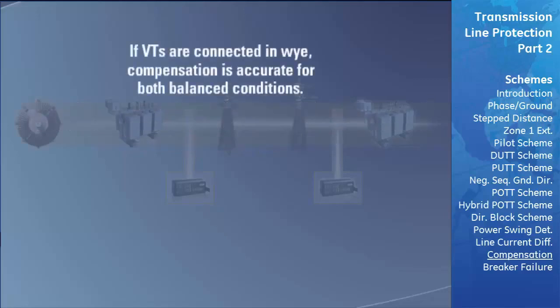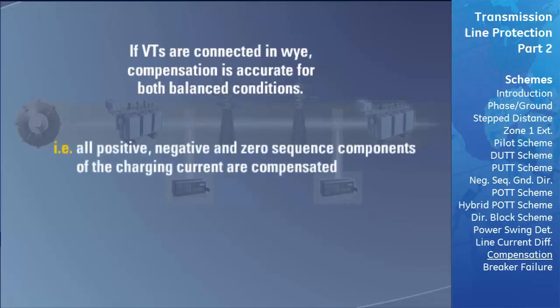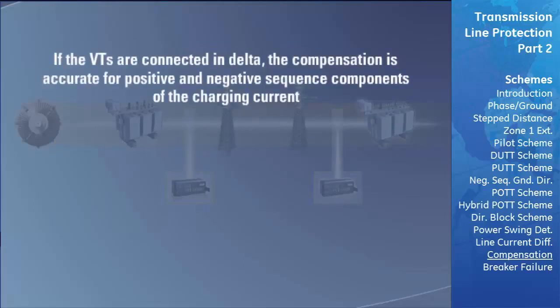If the VTs are connected in Y, the compensation is accurate for balanced conditions—all positive, negative, and zero-sequence components of the charging current are compensated. If the VTs are connected in delta, the compensation is accurate for positive and negative sequence components only. Since the zero-sequence voltage is not available with delta-connected VTs, the relay cannot compensate for the zero-sequence current.